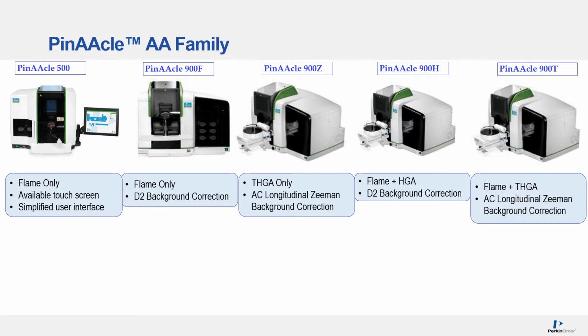Next is the PinAAcle 900H. This is a dual purpose unit. It has both flame and HGA furnace. Again, this has deuterium background correction, and because it is an HGA unit, it does not include the Zeeman correction on the furnace. And finally, we have the PinAAcle 900T, which is another dual unit, but this time it is a flame combined with a THGA furnace. So this does include the full Zeeman background correction on the furnace, as well as the deuterium background correction on the flame.